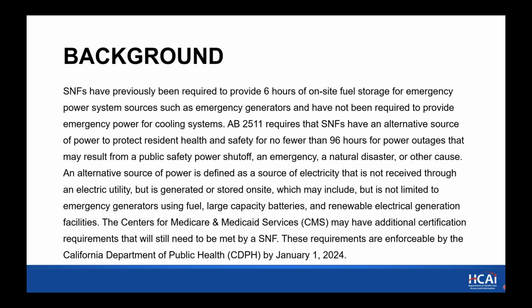So the background is that SNFs have previously been required to provide 6 hours of on-site fuel storage for emergency power system sources, such as emergency generators, and have not been required to provide emergency power for cooling systems. AB 2511 requires that SNFs have an alternate source of power to protect resident health and safety for no fewer than 96 hours for power outages that may result from public safety power shutoffs, an emergency natural disaster or other cause. An alternate source of power is defined as a source of electricity that is not received through an electric utility, but is generated or stored on site, which may include, but is not limited to, emergency generators using fuel, large capacity batteries, and renewable electrical generation facilities.